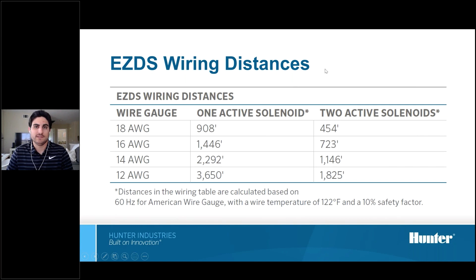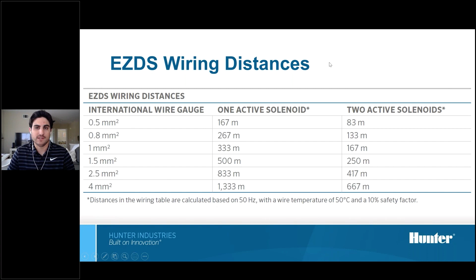So want to make sure that you're cognizant of how far you can actually go with how much stuff is turning on simultaneously there. So like to give full disclosure on the wiring distances, 1 solenoid, you can go max distance, 2 active solenoids, you cut it in half. Hey, if you're going to have 3 active solenoids, you cut it in half again. So that's kind of the gist of how we have our wiring distances available for the EZ decoder system. For any of my international friends out there, we got 2.5 millimeter square wire or 4 millimeter square wire. You can go about 833 meters or upwards of 1 kilometer on 4 millimeter squared wire there. So still a ton of real estate to be covered with the EZ decoder 2-wire system.